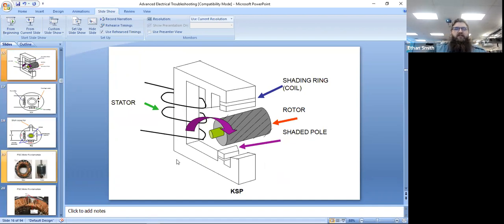So there's lots of different kinds of motors. This is what would be referred to as a shaded pole motor. These motors simply have an alternating current of wire wrapped around an iron core. That iron core, when you pass electrical current around it, becomes magnetic. It projects a magnetic field down into the rotor, which has another magnetic field induced in it because of that primary magnetic field. And so we get like and opposite charges attracting and repelling each other, which causes that motor to start spinning. So that's the most basic motor we see. See these a lot on inducer motors, things like that.